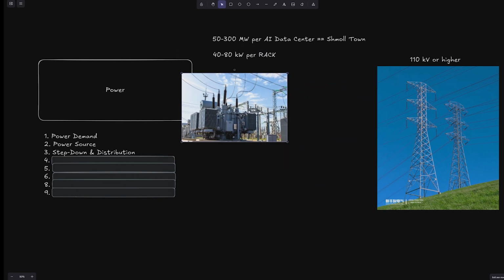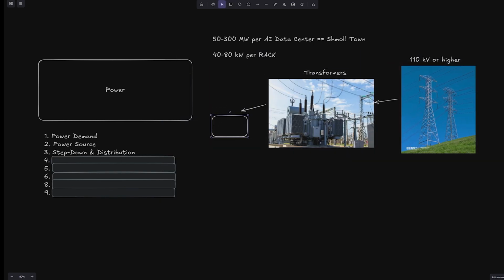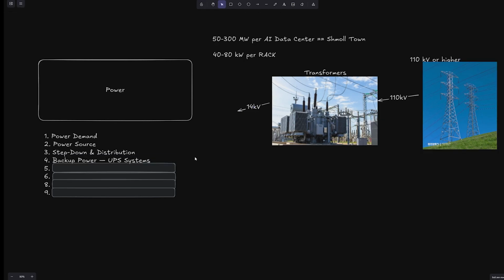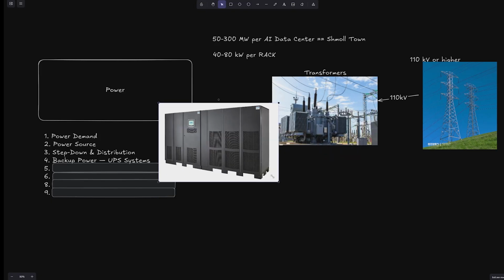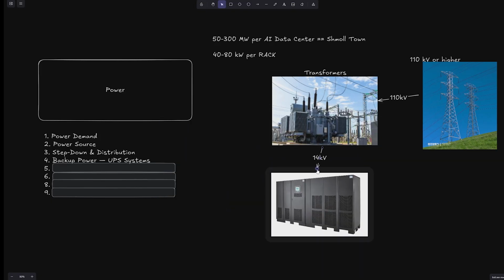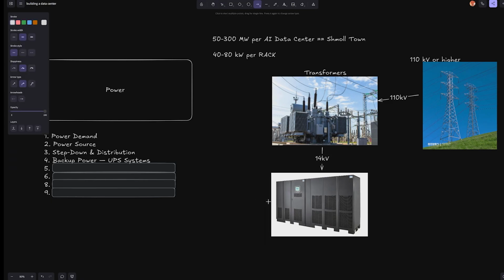High voltage power from the grid enters through transformers stepped down to medium voltage, around 14 kilovolts. Of course, we also have backup power. Between the grid and the servers sit uninterruptible power supplies, big battery banks. Between the grid and the servers, we also have UPS systems, uninterruptible power supplies. You can imagine big battery banks. They cover the few seconds between a grid outage and the startup of a diesel generator. Each UPS is redundant, N+1 or N×2, and it is constantly tested.